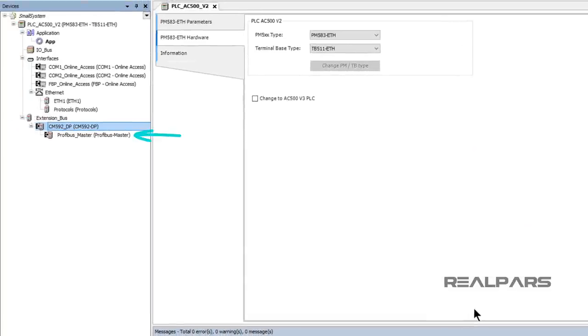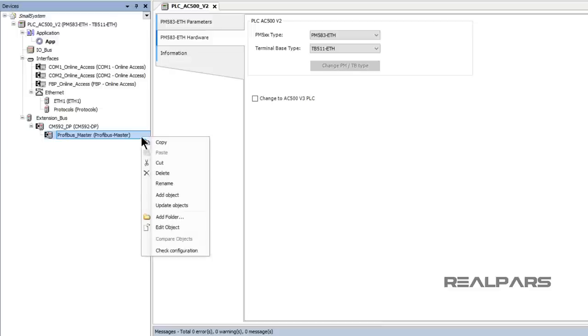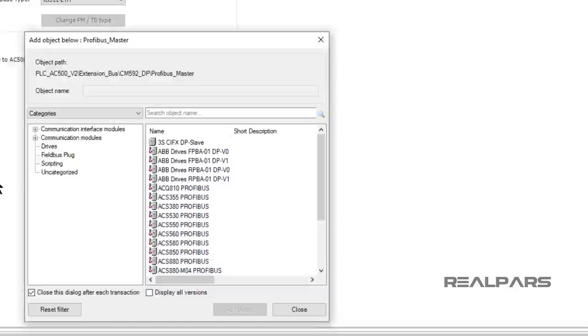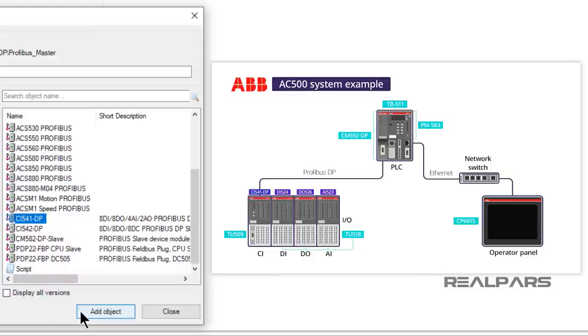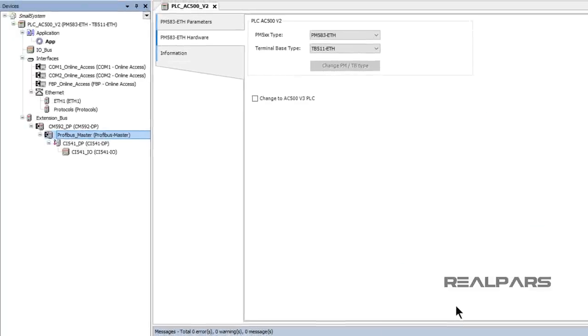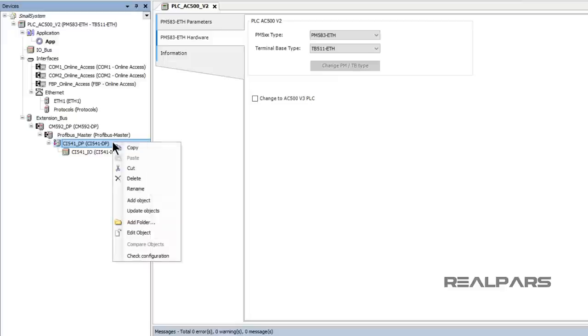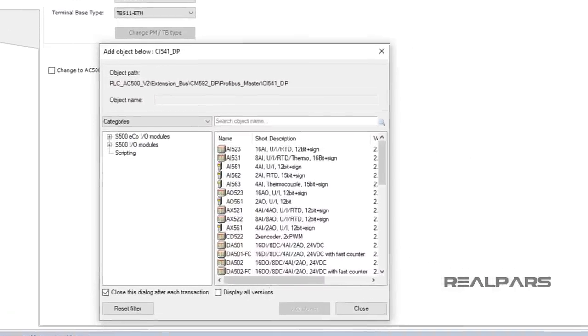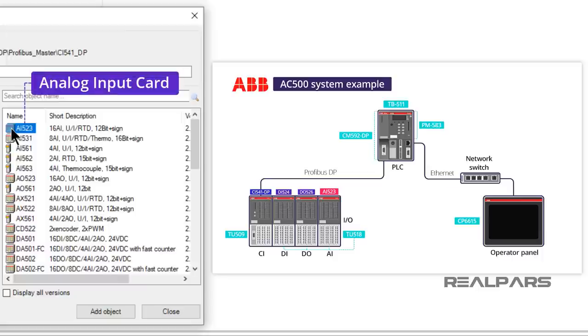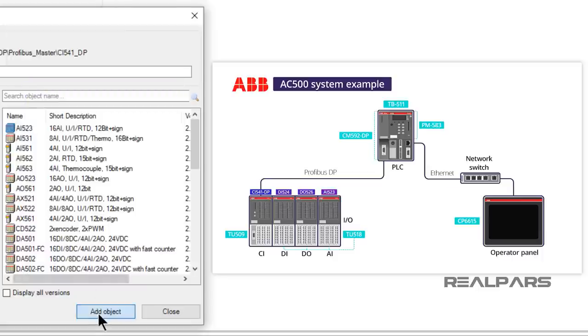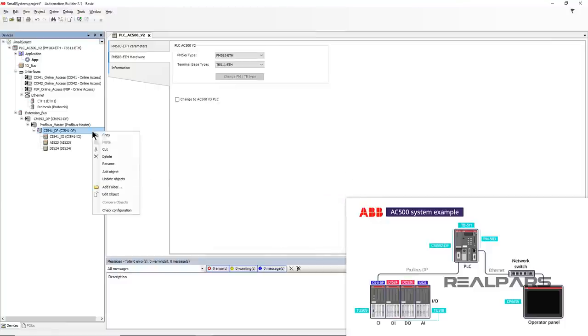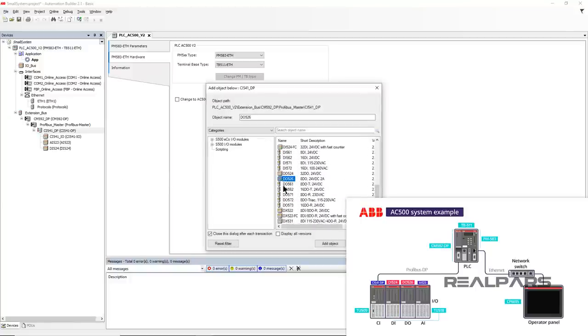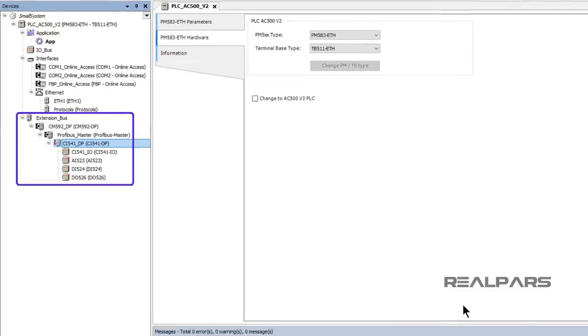The Profibus card now appears in the Device Tree. I right-click on Profibus Master and select Add Object. In the Add Object window, I select the CI541DP card and then select Add Object. The Device Tree updates and shows the CI541 module. I right-click on the CI541DP device and select Add Object, then select the AI523 analog input card from the Device List. I repeat this process to add the DI524 Digital Input Card and the DO526 Digital Output Card. I now see all of the hardware components listed in the Device Tree.